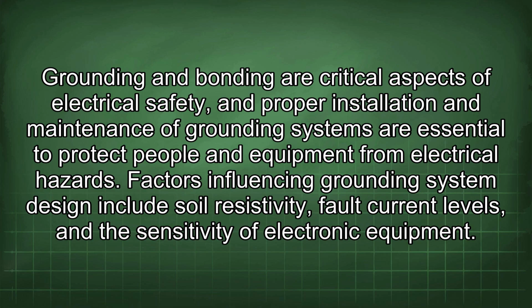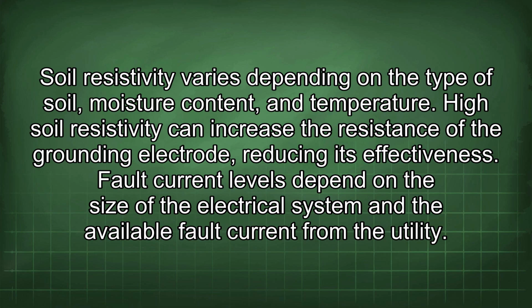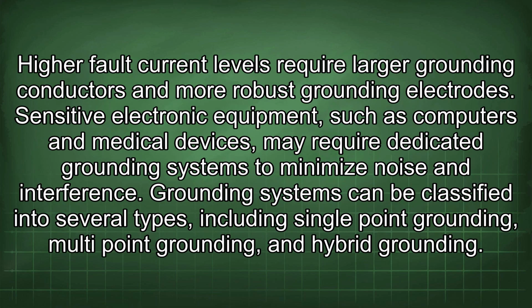Factors influencing grounding system design include soil resistivity, fault current levels, and the sensitivity of electronic equipment. Soil resistivity varies depending on the type of soil, moisture content, and temperature. High soil resistivity can increase the resistance of the grounding electrode, reducing its effectiveness. Fault current levels depend on the size of the electrical system and the available fault current from the utility. Higher fault current levels require larger grounding conductors and more robust grounding electrodes. Sensitive electronic equipment, such as computers and medical devices, may require dedicated grounding systems to minimize noise and interference.